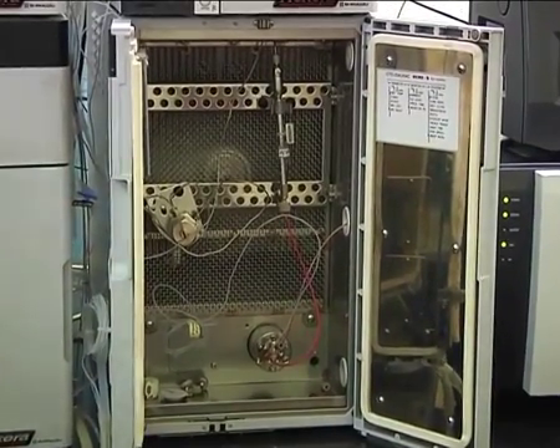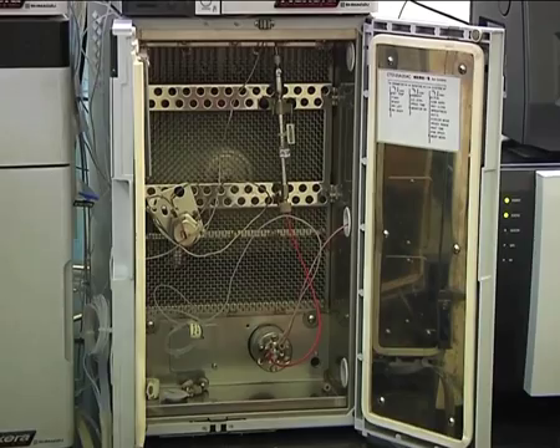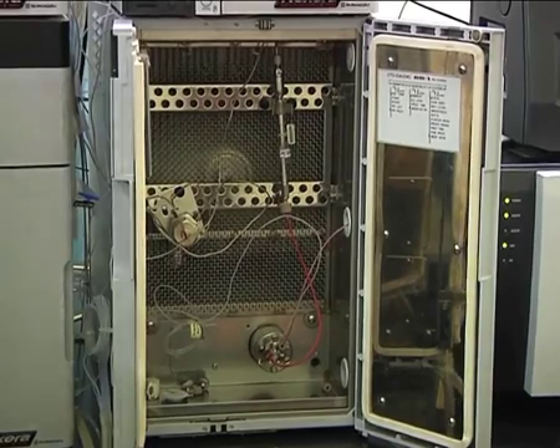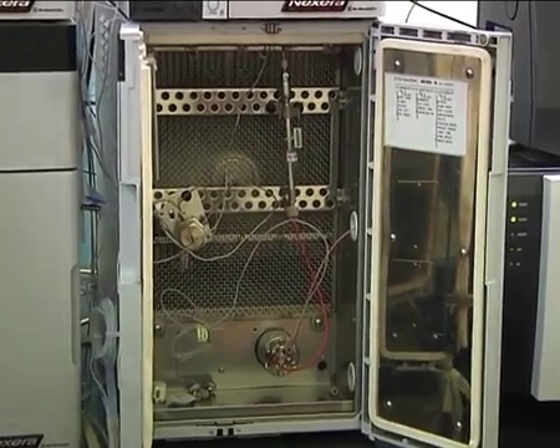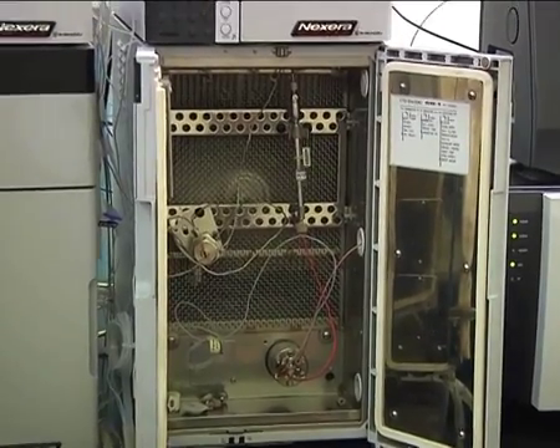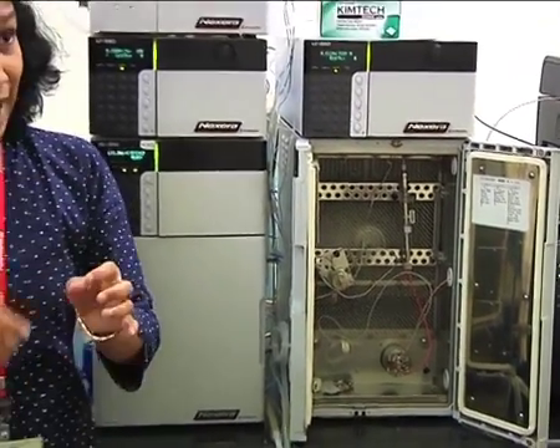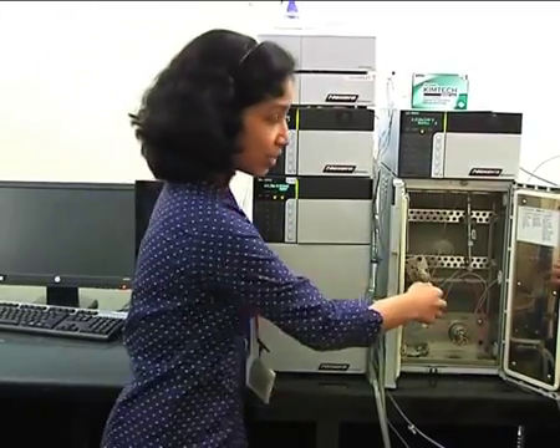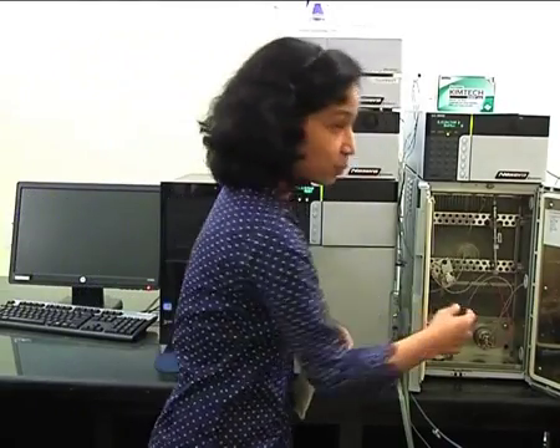Generally, I told you this is a fast HPLC system. The main use of a fast HPLC system is reduction in the analysis time. So if my analysis time is only 5 minutes or 10 minutes, and in that I want to do gradient analysis, that means my A to B concentration is continuously changing. My mixer should be so efficient that within that smaller amount of time it should give me proper mixing. So this mixer is specifically designed with microreactor technology. Its mixing efficiency and mixing accuracy from run to run is very good.